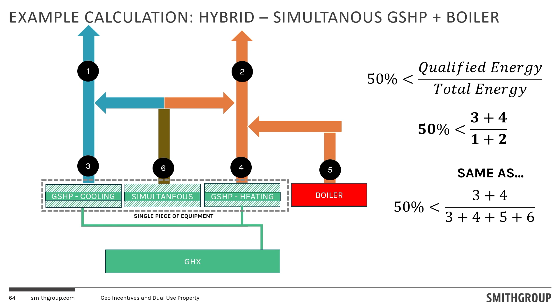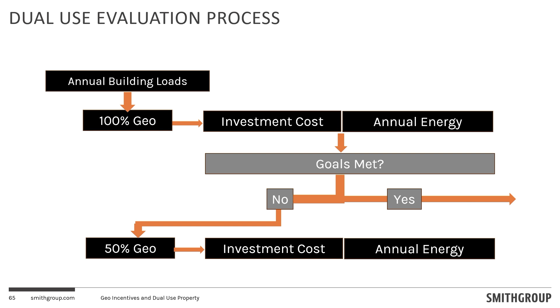So one way of thinking about this is you take your annual loads, maybe you look at the largest bore field, and you look at the investment cost of that, annual energy of that, maybe how much dual use you'll be able to qualify for, and you look at if your goals are met. Then maybe you iteratively move through that process and down until you hit the 50% cliff, and you stop when you meet your goals. So sometimes you do more than 50% because you want to meet certain energy goals, or maybe it's a LEED building and you need the larger bore field. So tomorrow I'll be talking about more of the analysis workflow that I use to do this, a little bit more of a case study on that. So if you want to join.